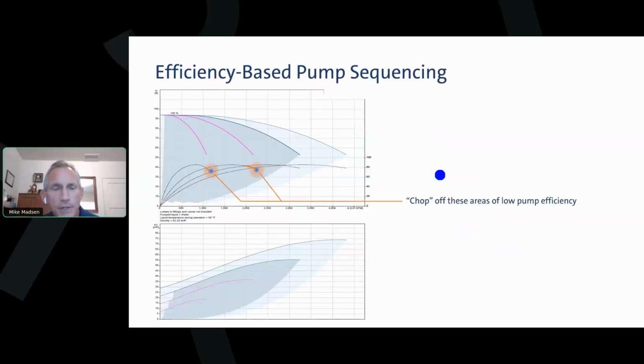So the other thing that us manufacturers can do is something called efficiency-based pump sequencing. It's a simple term. You can either program your controller, or have the controller pre-programmed, where you load a pump curve in and you load an efficiency curve in. And all efficiency-based pump sequencing means is this is pump 1, this is the efficiency of pump 1, this is pump 1 plus pump 2, this is the efficiency of 1 and 2.